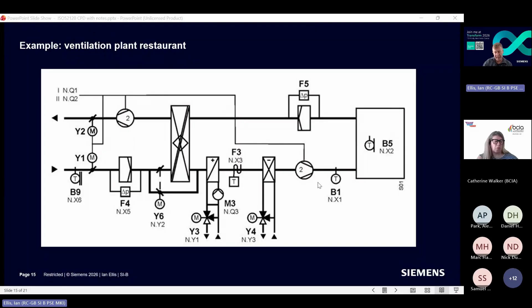But if I want to do the right thing, if I'm doing a retrofit, or if this was still in the design stage, and I said, well, no, I want to make that better, I want to make that more energy efficient, how can I do that? I defer to the standard. It would tell me to add some form of occupancy detector within that space. Even better would be an air quality detector, because then I can look at the CO2 levels and control not just on whether there's anyone in there or no one in there, but how many people are in there, and what I need to do in terms of the ventilation and so on.